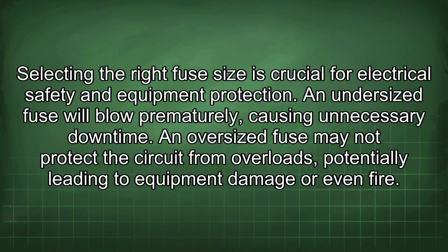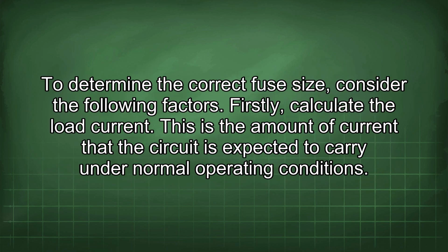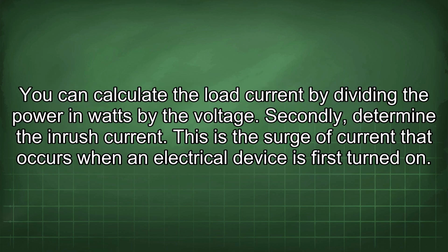An undersized fuse will blow prematurely, causing unnecessary downtime. An oversized fuse may not protect the circuit from overloads, potentially leading to equipment damage or even fire. To determine the correct fuse size, consider the following factors. Firstly, calculate the load current. This is the amount of current that the circuit is expected to carry under normal operating conditions. You can calculate the load current by dividing the power in watts by the voltage.